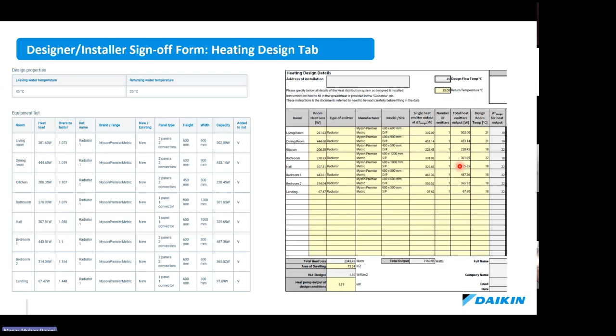And then the third sheet on this sign-off form is the radiator output conversion tab. This is where we basically copy the outputs of the radiators from the manufacturer's data sheet. So you would have the heat output from the manufacturer over there. You'd copy it based on the size and paste it in here. And then the delta T of that, which is normally 50. And you have a conversion factor here, and that's the formula. And then it automatically calculates the value. So basically, the values in this tab should match the values in the previous tab. So we see 302, 453. So that adds up and matches the ones over here.